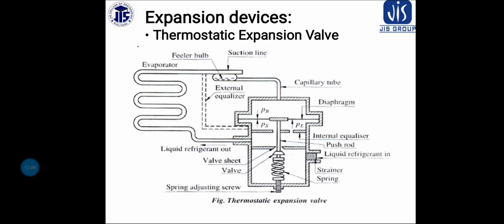As a result, the pressure and degree of superheat in the evaporator increase. The increase in superheat causes the valve to open more and allow more refrigerant to enter the evaporator. At the same time, the increase in suction pressure also enables the compressor to deliver increased refrigerating capacity.